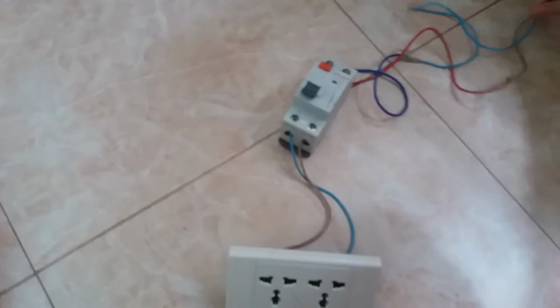The second way is very simple. We have to create a leakage current, meaning we let the hot wire touch the earth. So the leakage current will be great and the circuit breaker will trip. Now I will plug in.